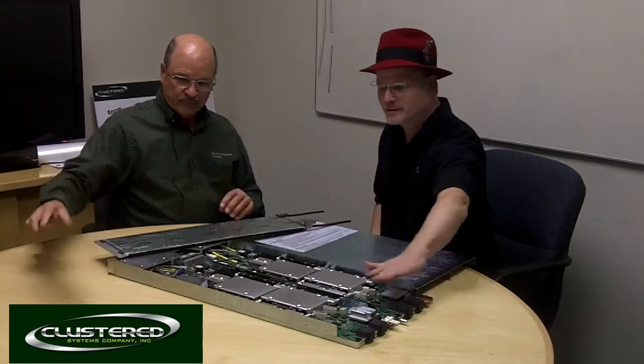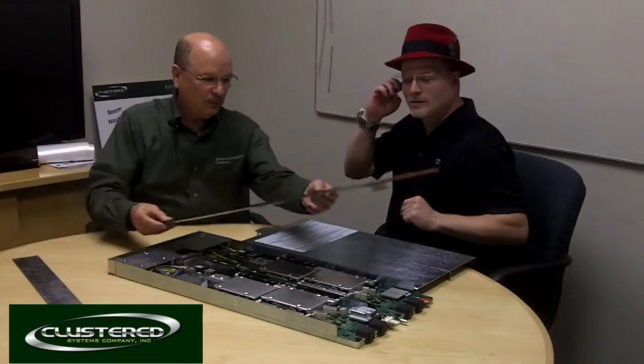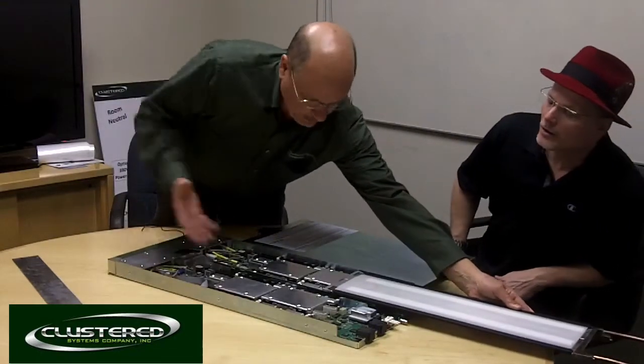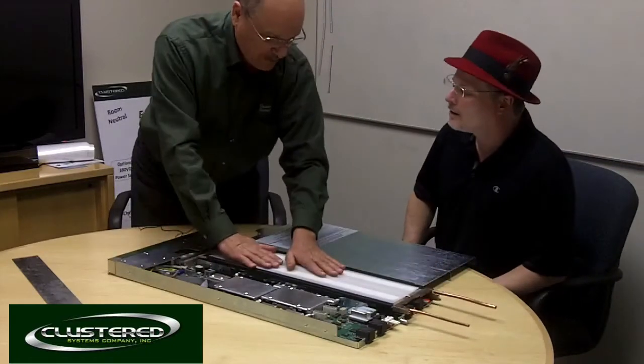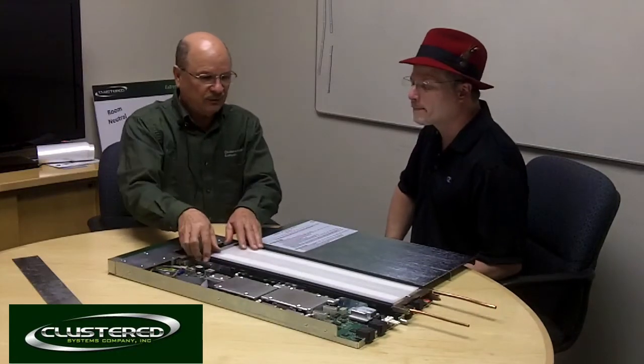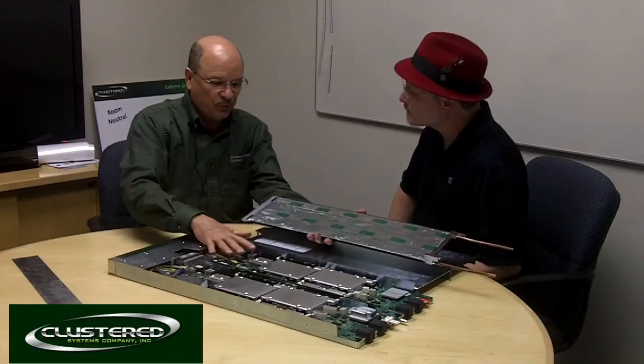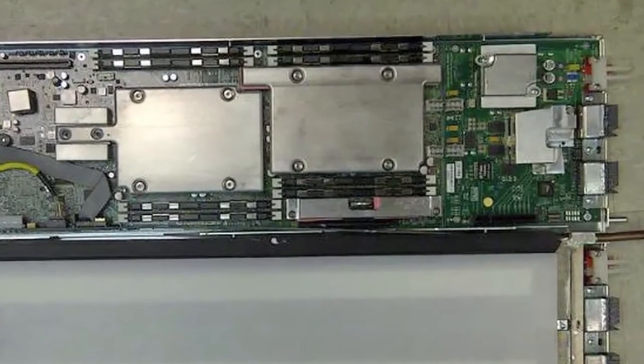You place this full blade over this node here and you take the heat away. When it's in operation, the blade inserts like this — as the blade goes back, the cold plate is inserted, and it sits on top of all the hot elements. It not only cools those directly by conduction, but other components on the motherboard are all cooled by convection because this makes the entire environment of the blade one temperature. So we really don't have to worry about the lower-power components at all.